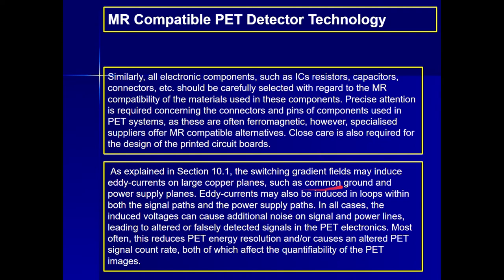The switching gradient fields may induce eddy currents on large copper planes such as common ground and the power supply planes. Eddy currents may also be induced in loops within both the signal paths and the power supply path. In all cases, the induced voltages can cause additional noise on signal and power lines, leading to altered or falsely detected signal in the PET electronics. Most often, this reduces PET energy resolution or causes an altered PET signal count rate, both of which affect the quantifiability of the PET images.